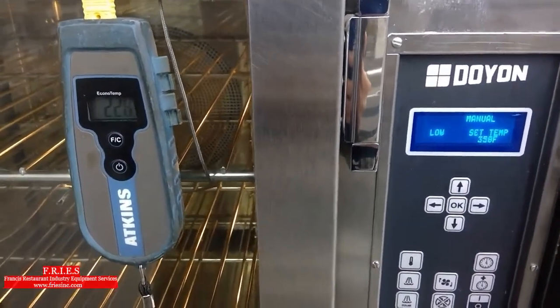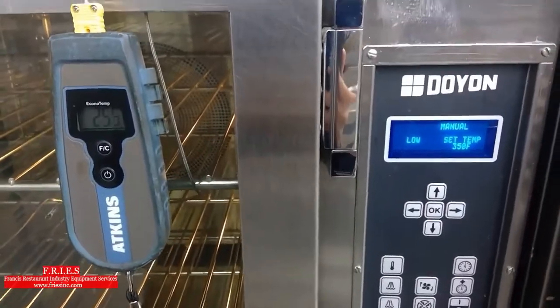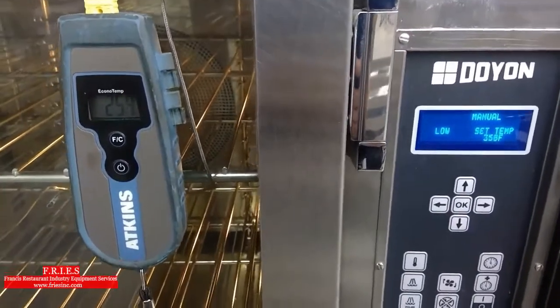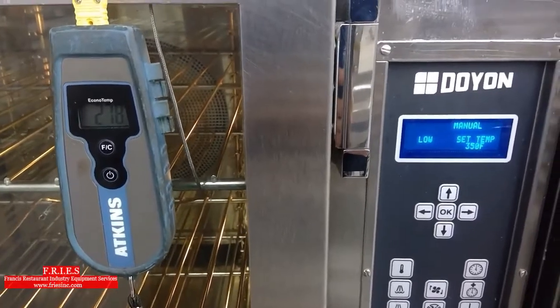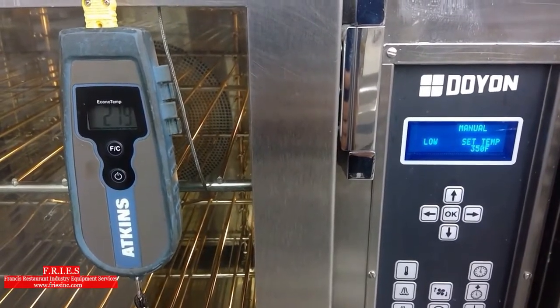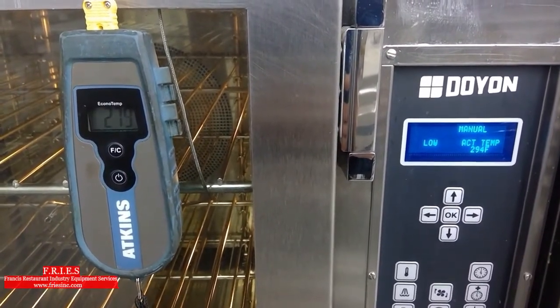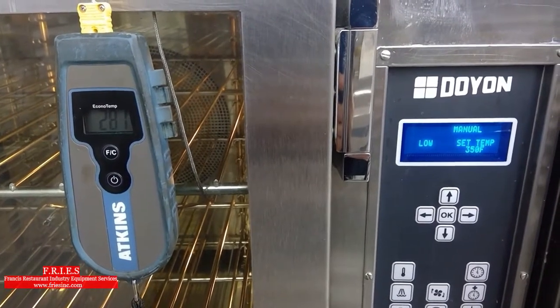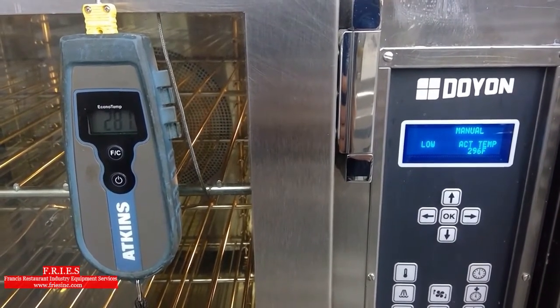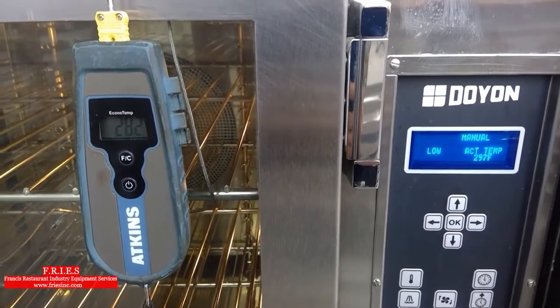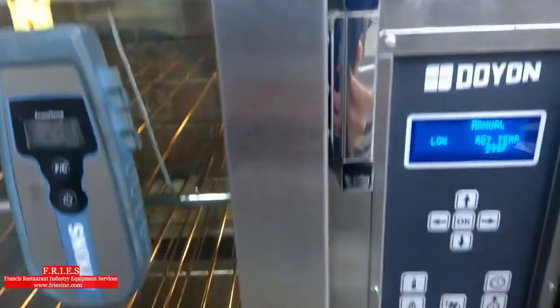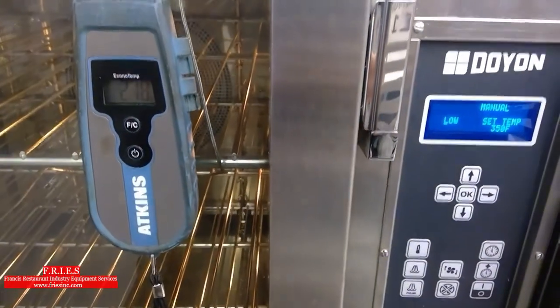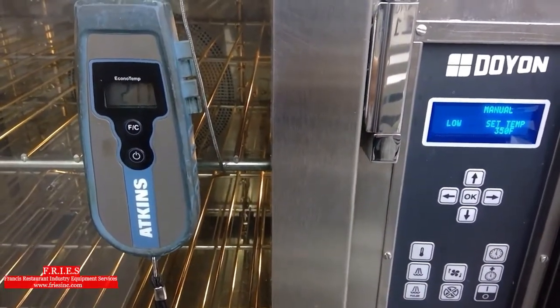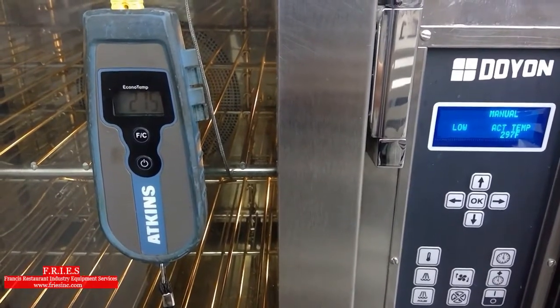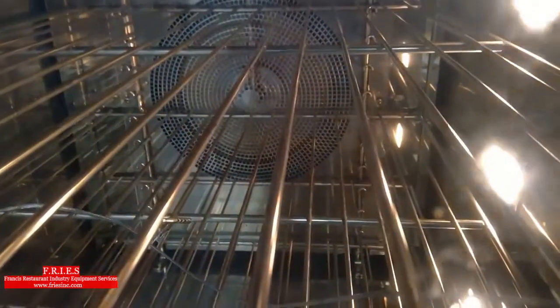Just gonna hit the fast forward one more time here. Alright, so listen carefully here. Burner just shut off. Blower is still running. So we have found our issue here. This burner should be running right now. We're still calling for heat.